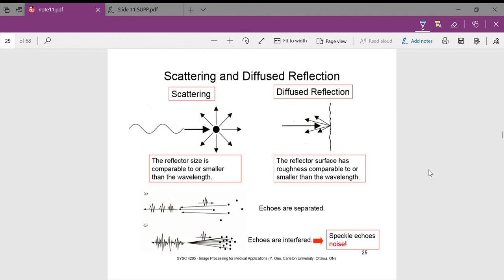Scattering is the process by which secondary spherical waves are generated as the wave propagates. Many targets within the body are much smaller than the acoustic wavelength. For these targets, the geometric optics equations for reflection and refraction do not hold. Instead, we assume that when these targets are excited by an incident acoustic plane wave, they vibrate as small spherical bodies giving rise to spherical waves whose amplitude is some fraction of the incident wave amplitude. Reflection can be categorized as either specular or diffuse.